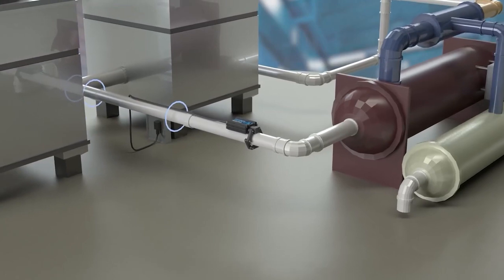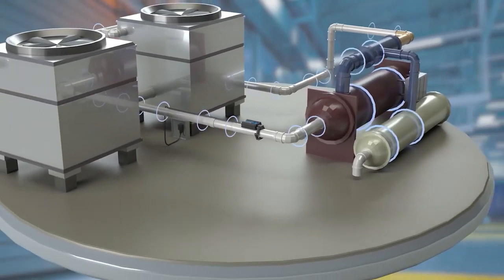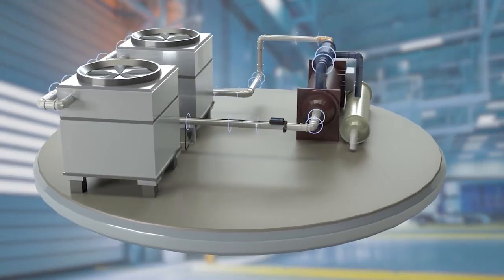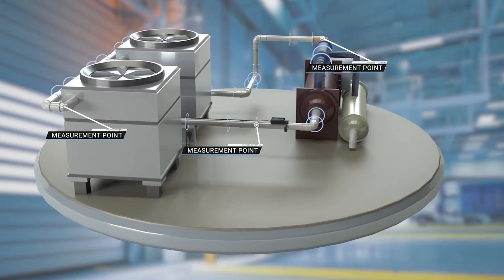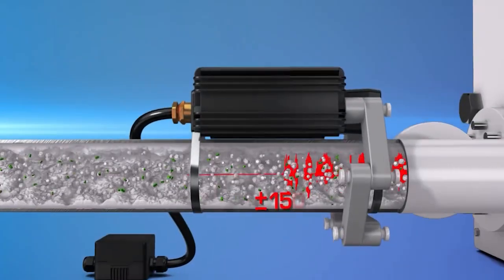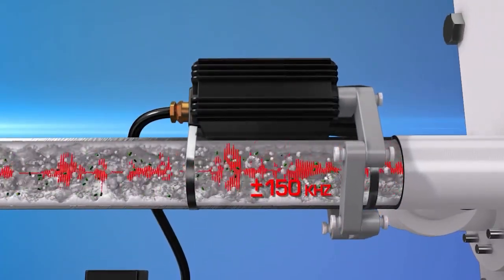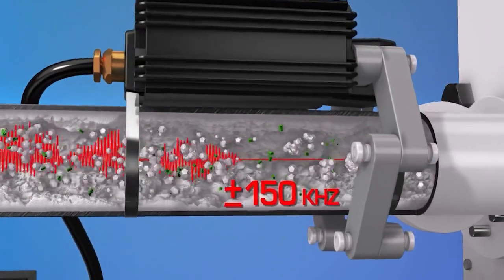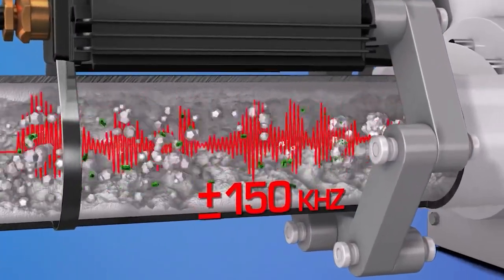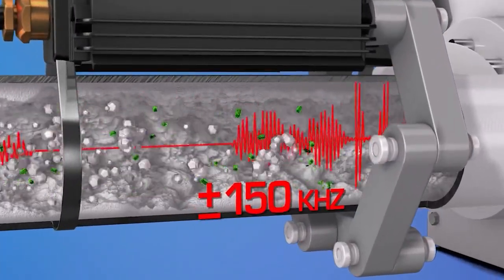As mentioned earlier, the hydropath signal gradually dissipates as it travels further away from the unit. To ensure the signal is treating the entire system, we need to measure its strength at various points throughout. While peak-to-peak voltage measures the hydropath signal strength at the point of induction, voltage potential is the transducer's ability to propagate the signal throughout the system, or in other words, the amount of potential energy between two points in a circuit.